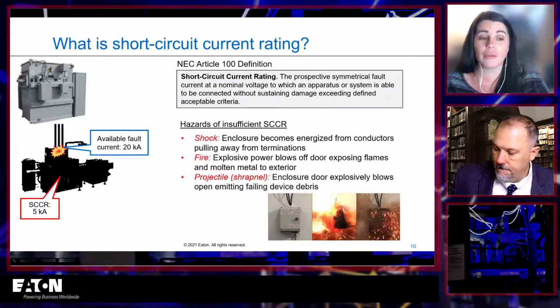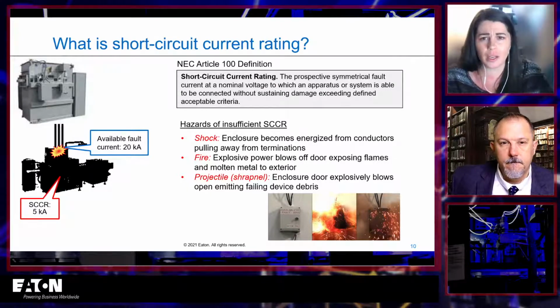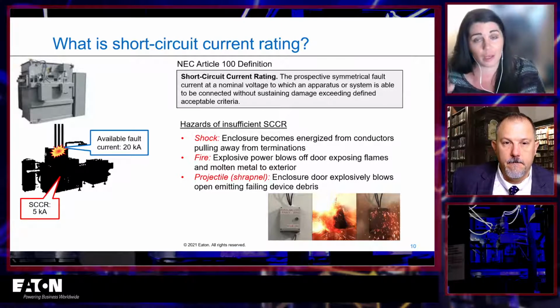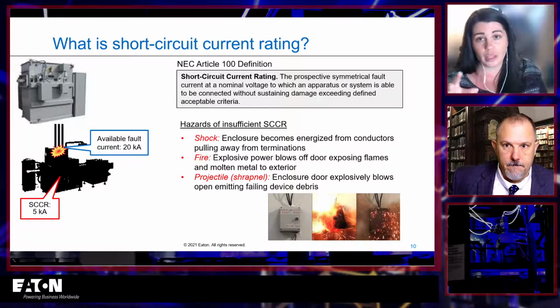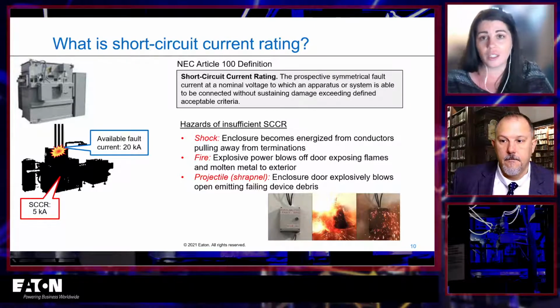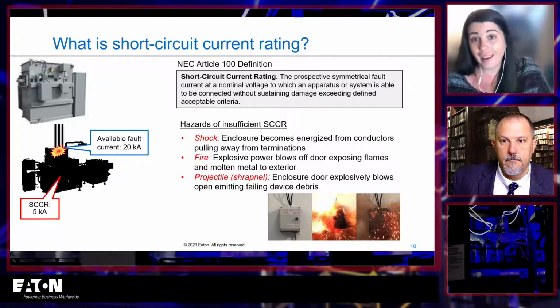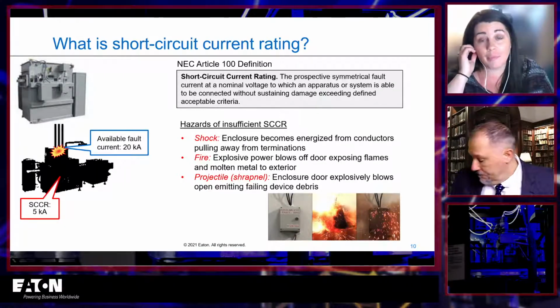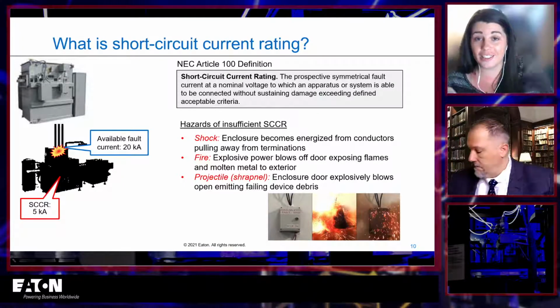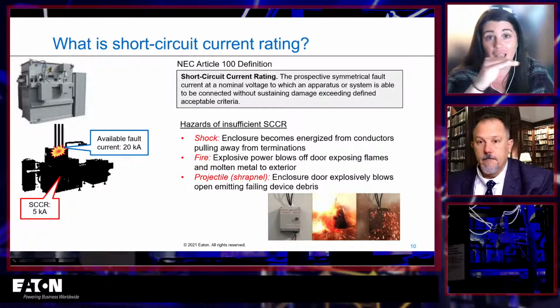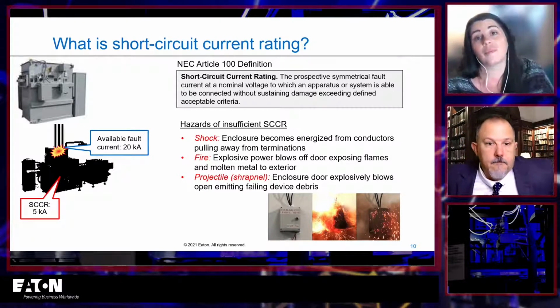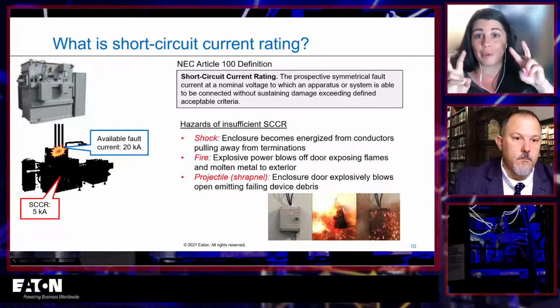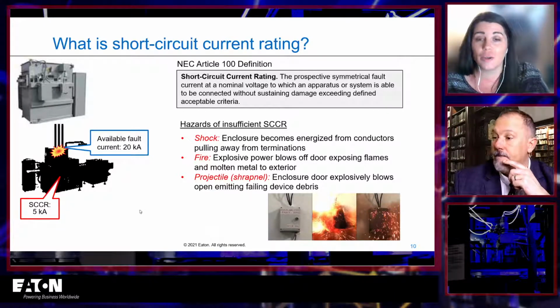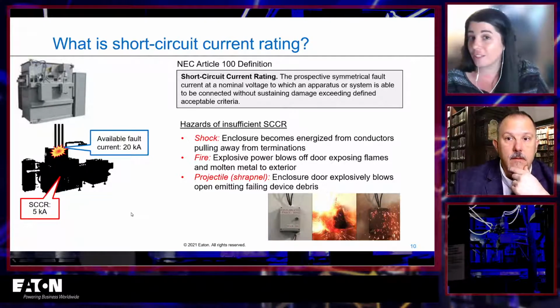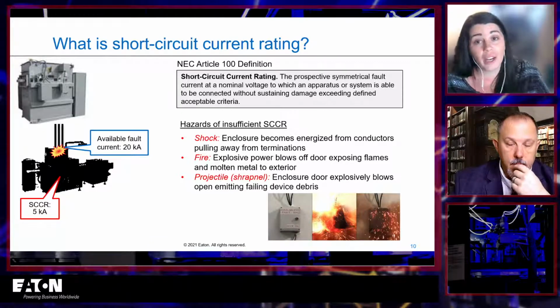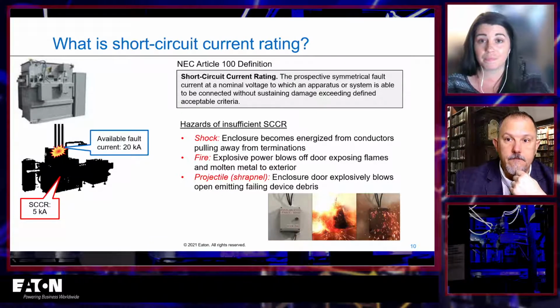I've had a number of times people call me up and say, "Hey, something happened. I had a short circuit inside my piece of equipment, and this thing burned up, and I can't use it again. Was the short circuit current rating wrong?" And it's not necessarily. That might be exactly what it's meant to do. It's below the threshold of hazard. It's deemed the acceptable damage, I guess, whenever you have a short circuit. It clears the fault, hopefully, safely. But you might have to do some equipment modification.